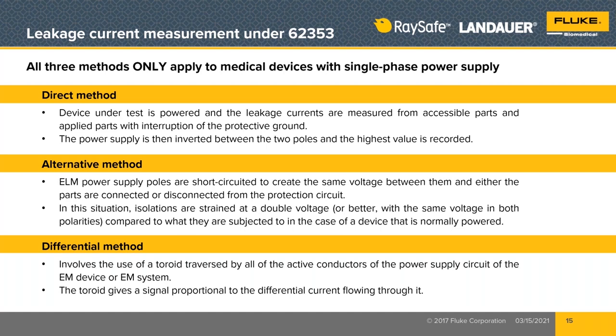In the alternative method, the power supply poles are short-circuited to create the same voltage between L1 and L2, and either the parts are connected or disconnected from the protection circuit, so ground would be lifted. In this situation, isolations are stressed at a double voltage or better with the same voltage in both polarities.